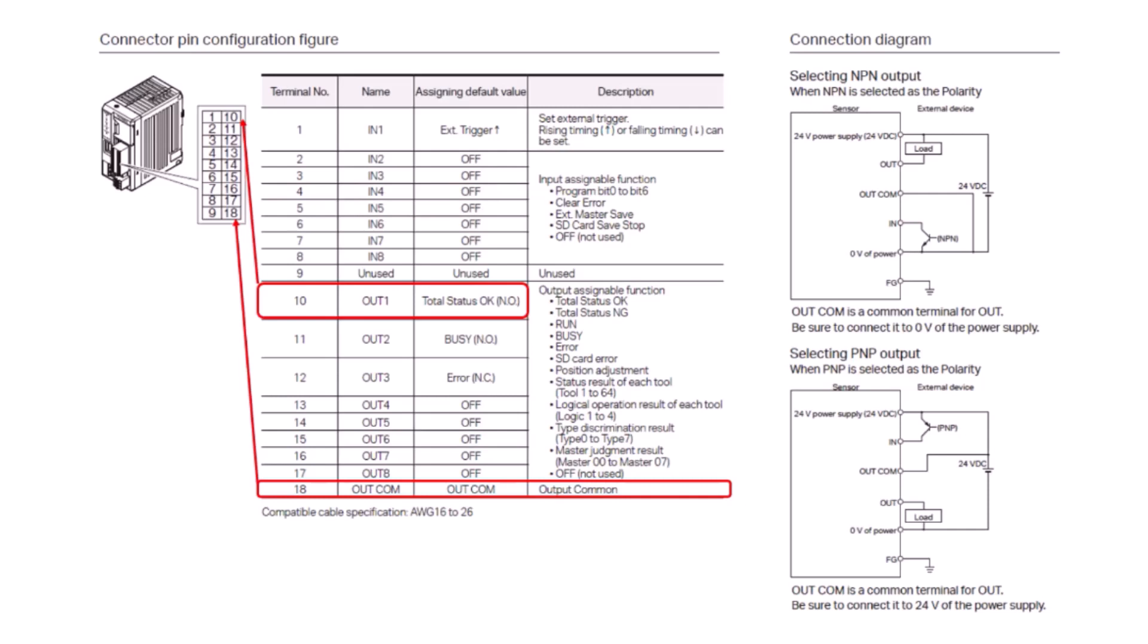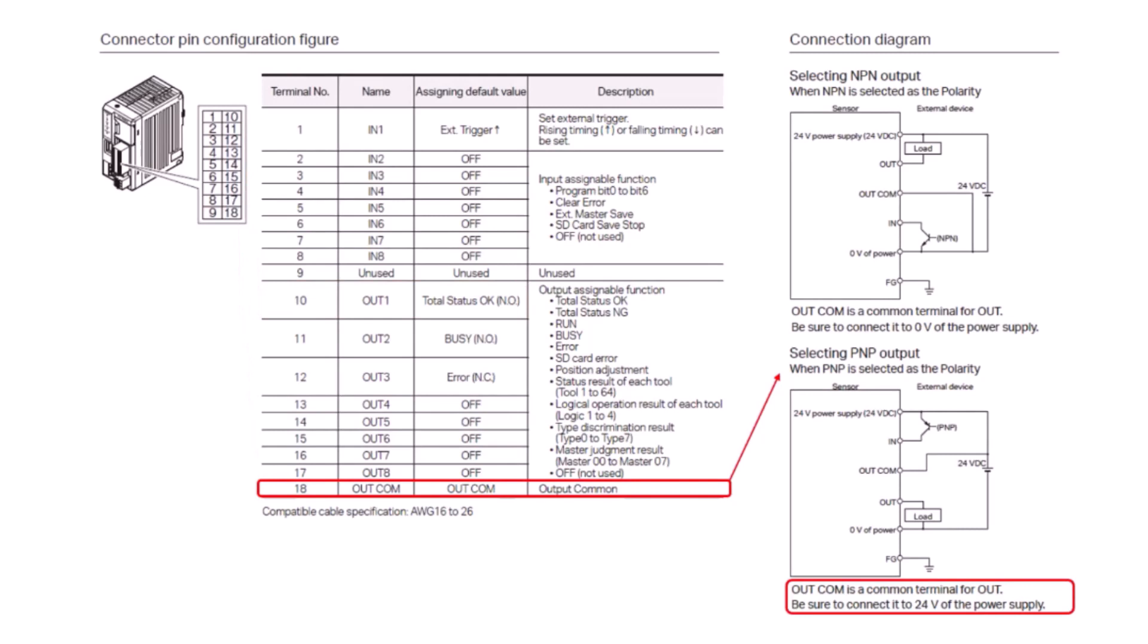Where the output common will connect is going to depend on what polarity you select. For example, if you want a PNP output for 24 volts, your output common is going to connect to the 24-volt side of the power supply.